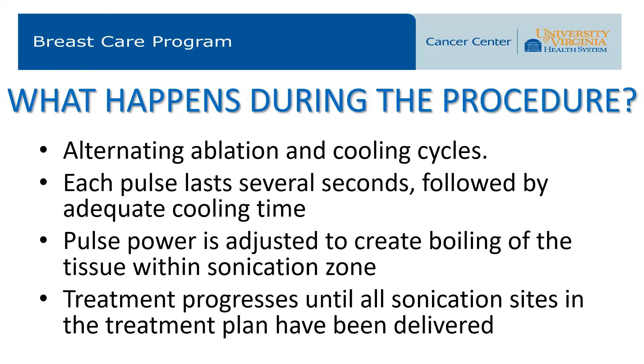So what does it look like? Well, on the device, prior to treatment, the fibroadenoma looks like this. A sonication pulse is then delivered, and this results in a hypoechoic mark as depicted here following the sonication. The treatment head then moves to the next sonication site, and another pulse is given. This heats up the second area in the treatment plan. The device then moves to the third area in the treatment plan. Another sonication pulse is given, and this continues till all of the sites in the treatment plan are sonicated.